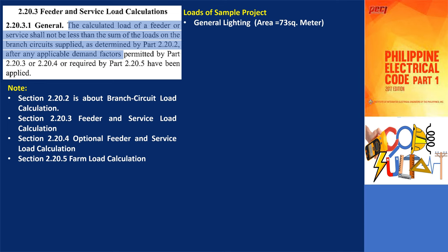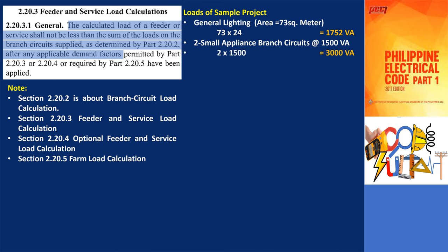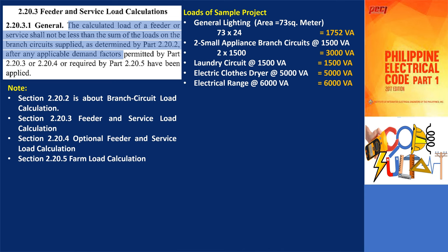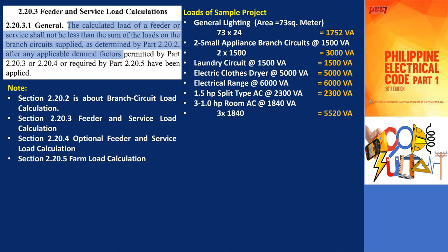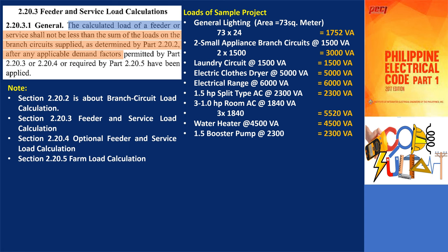Here are the loads of our sample project. For general lighting, we have 1,752 volt amperes, which includes receptacle outlets in general areas, bathroom circuits, garage circuits, and lighting loads. There are two 20-ampere small appliance branch circuits at 1,500 volt amperes each. Laundry circuits at 1,500 volt amperes. Electric clothes dryer at 5,000 volt amperes. Electrical cooking range at 6,000 volt amperes. 1.5 horsepower split type air conditioning unit, 3 1.0 horsepower room air conditioning units, 1 4.5 kW storage water heater, and 1.5 horsepower booster pump. The rules shall not be less than the sum of all loads after applying demand factors.